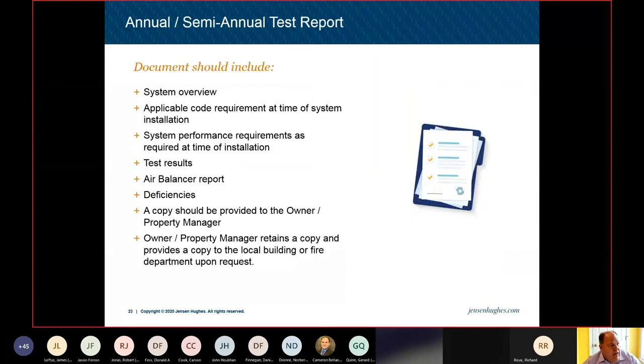So the documents that should be included in that report, the system overview, it's very important to understand the applicable code and the requirements at the time of the system installation. We're not trying to make an existing system meet new code requirements. So you have to have an understanding of that originally, and that's what's so vital about that. System performance requirements, as required at the time of installation, you want to cite that, so that becomes part of the annual, semi-annual test report. Your lead testing agency or smoke control special inspector for the existing system can help put that together.